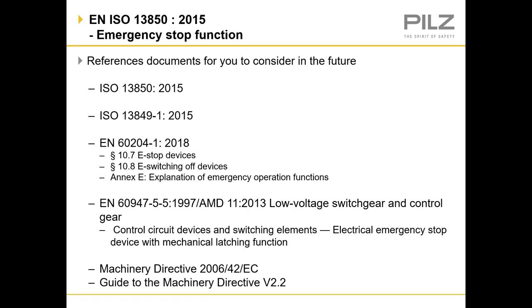It's useful to know that standard 13849 was also updated in 2015. We will be looking into standard EN 60204 part 1, which was revised in 2018. Section 10.7 makes mention of emergency stop devices, and section 10.8 considers emergency switching off devices and their operation functions, which we're going to look at later on. Standard EN 60947 part 5 had an amendment in 2013 and covers the manufacture of low voltage switchgear and control gear, which also includes emergency stops.